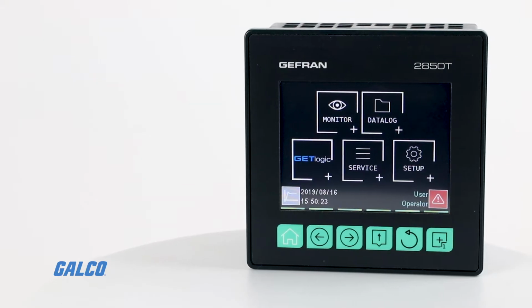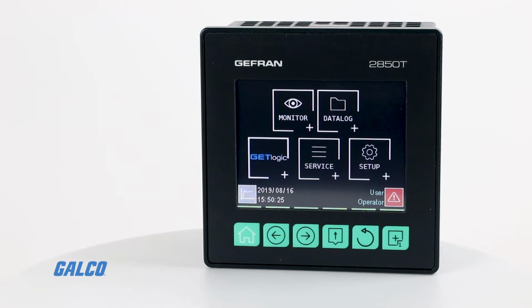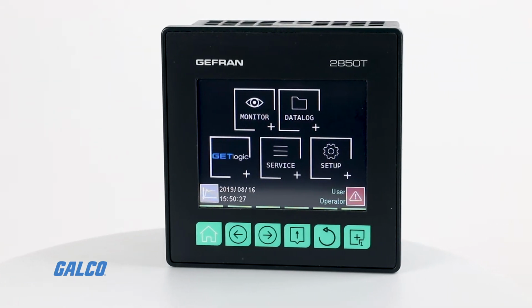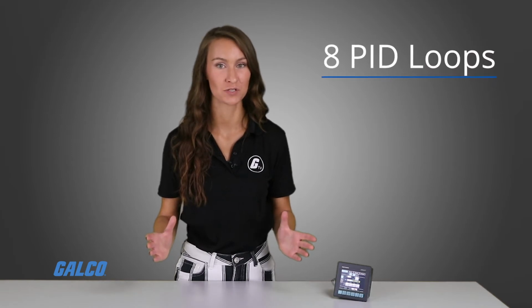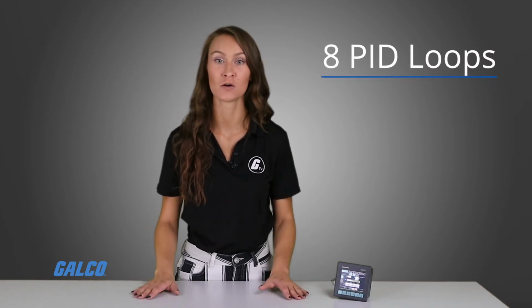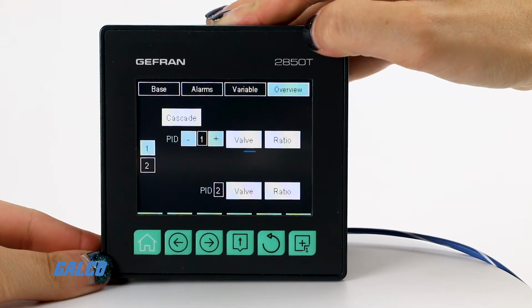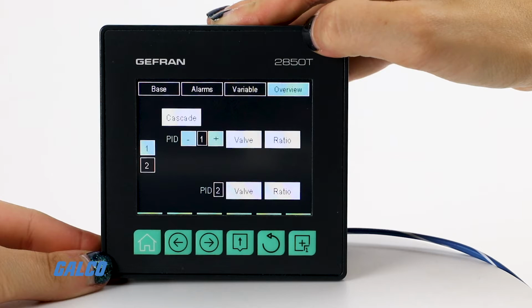It features a 3.5-inch touchscreen and 6 function keys to help make navigation and operation a breeze. Up to 8 PID loops can be managed by this controller, and they are fully configurable. Each PID loop can be used as a control for a single loop, a valve, or control ratio, and it can be connected to the profile programmer or used as a cascade controller.